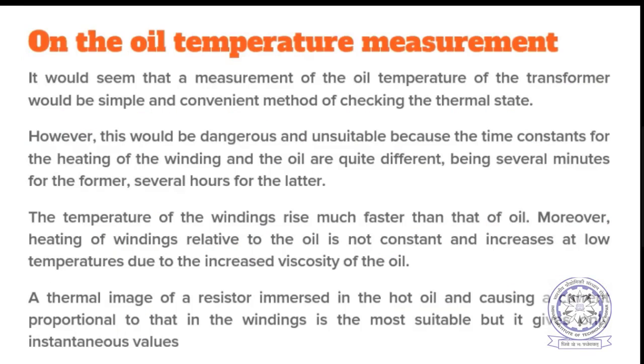Next, on the oil temperature measurement. Now, how can the thermal condition of the transformer be assessed? It may seem that measuring the oil temperature of the transformer is simple, right? We can keep a temperature sensor in the oil. It is very simple and convenient. So oil temperature can be measured and the thermal state of the transformer can be assessed. Okay, this is the temperature, so we should not overload, something like that.